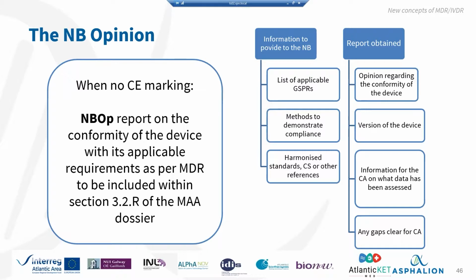Okay, and then you will receive back a report. In this report, the notified body will give their opinion regarding the conformity of the device. The notified body is going to assess if the device complies or not with the regulation. This report is also going to list which version of the device has been evaluated, and it's going to have all the information for the competent authority on what data has been assessed.